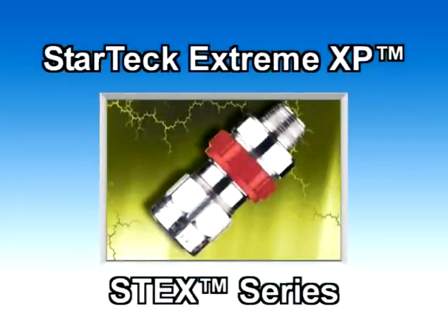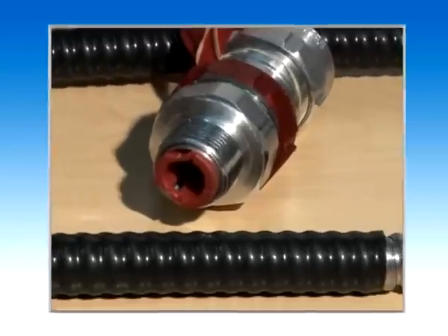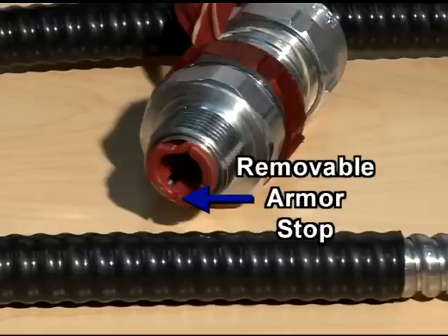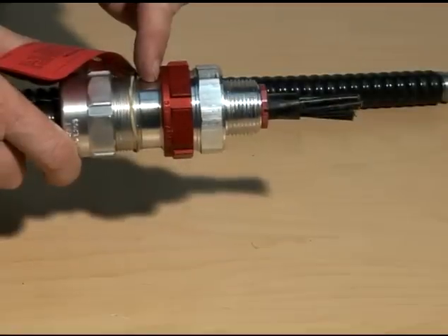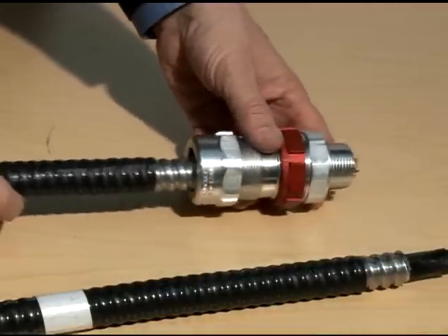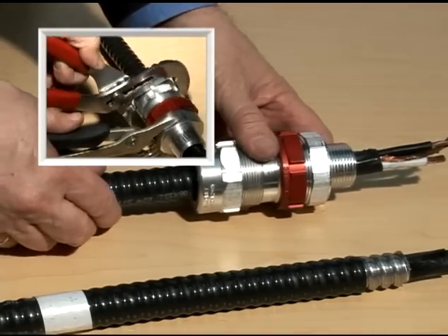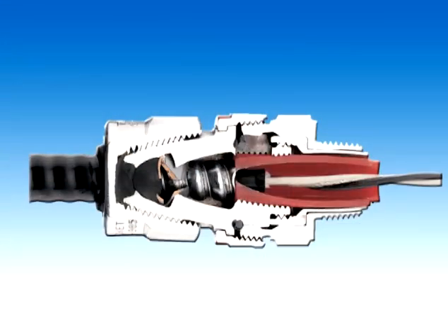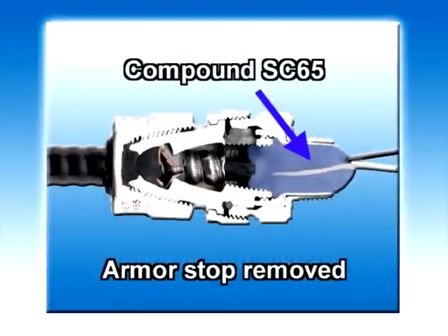Presenting the StarTech Extreme XP STEX Series Fitting. The StarTeck Extreme XP explosion-proof fitting features a removable armor stop which allows the fitting to accommodate a broad range of cable sizes and can replace up to three conventional TECK fittings. For smaller cables, you keep the armor stop, and for larger cables, you remove the armor stop. Once the cable is properly seated into the StarTeck Extreme fitting, tighten the gland nut to secure the fitting on the cable. If the armor stop is still in place because a smaller cable is being installed, you will need to remove it before applying the SC4 Kit Liquid Sealing Compound or the SC65 Putty Compound.